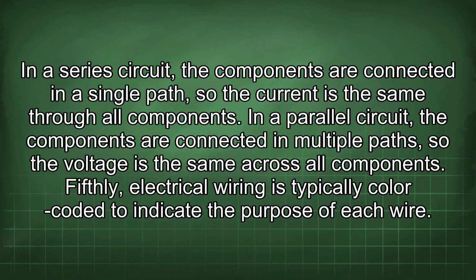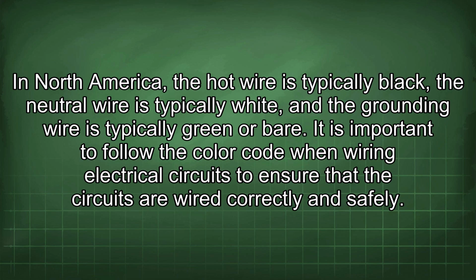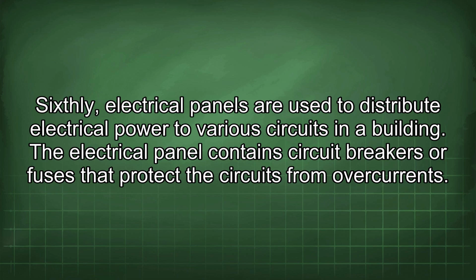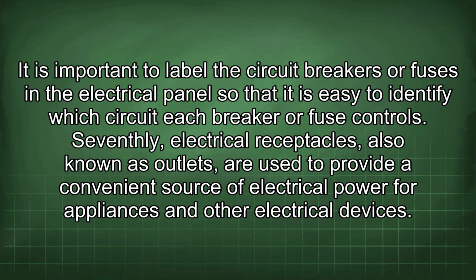components. Fifthly, electrical wiring is typically color-coded to indicate the purpose of each wire. In North America, the hot wire is typically black, the neutral wire is typically white, and the grounding wire is typically green or bare. It is important to follow the color code when wiring electrical circuits to ensure that the circuits are wired correctly and safely. Sixthly, electrical panels are used to distribute electrical power to various circuits in a building. The electrical panel contains circuit breakers or fuses that protect the circuits from overcurrents. It is important to label the circuit breakers or fuses in the electrical panel so that it is easy to identify which circuit each breaker or fuse controls.